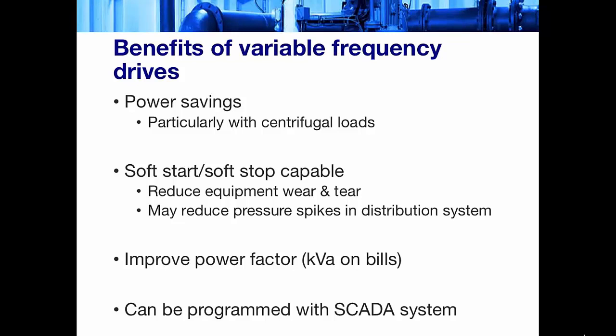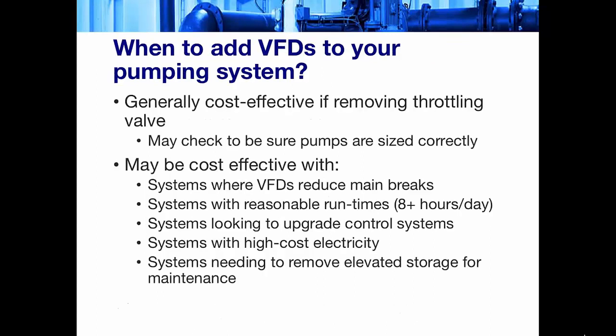So if you know you have pressure spikes within your distribution system, installing variable frequency drives can be a huge win for you. They can also improve power factor. So if you have KVA on your bills and are being charged for it, variable frequency drives might help you out there. And then they're readily programmable with programmable logic controllers and SCADA systems. So when should we add them? The next slide gives you some things to consider.